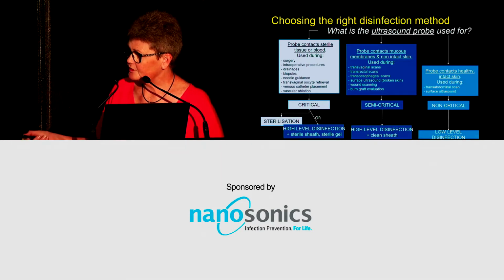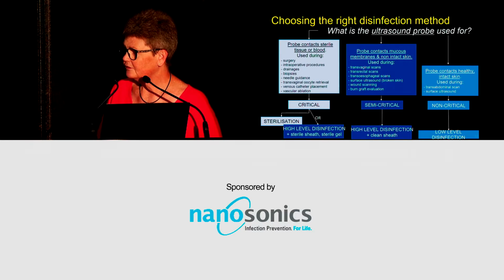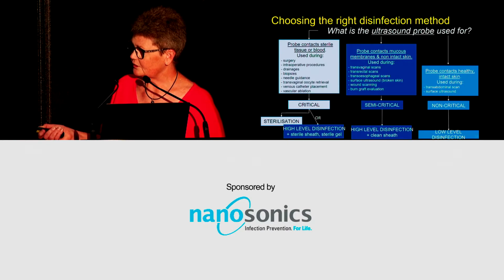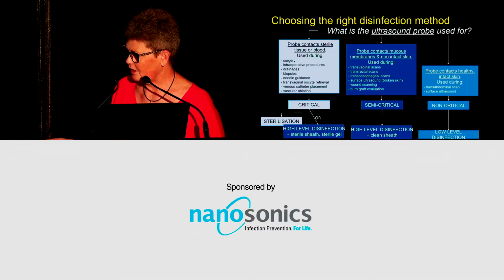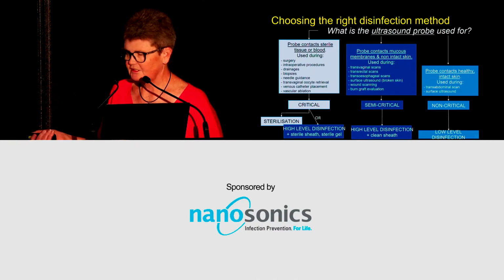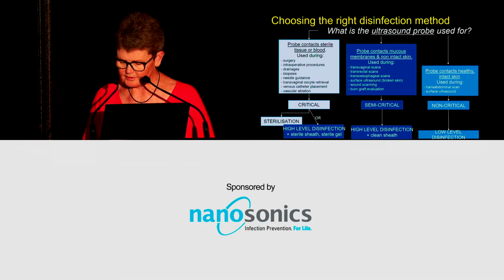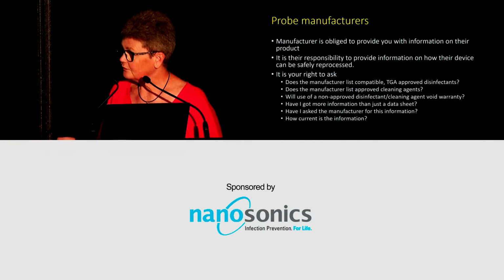And so think again in a modified Spaulding classification. If the probe has contact with sterile tissue or blood and is used during any of these procedures, it's inevitably a critical device and therefore should be sterilised unless it's heat sensitive or too delicate. Then it can have high level disinfection, but of course you then need to use a sterile sheath and only ever use gel which is confirmed to be sterile and not contaminated. If the probe, however, is having contact with mucous membranes or non-intact skin, in any of these types of procedures, it's a semi-critical item and therefore should be appropriately reprocessed by having high level disinfection and the use of a clean sheath. If the probe has contact only with healthy intact skin, such as a transabdominal ultrasound or a surface ultrasound, it definitely is a non-critical item and low-level disinfection should be sufficient for its reprocessing. So those are two ways that I've done that.